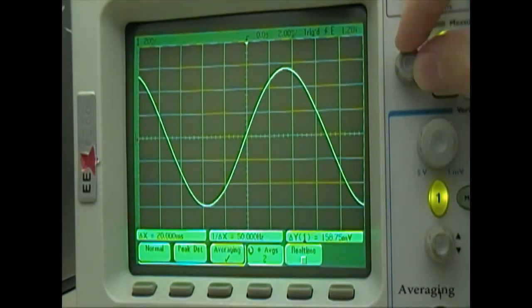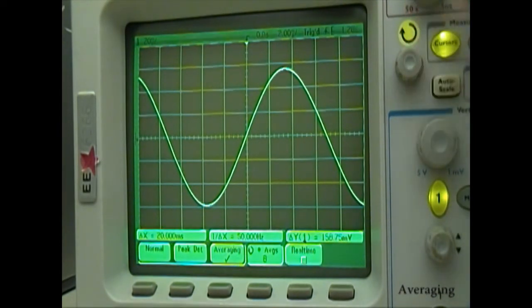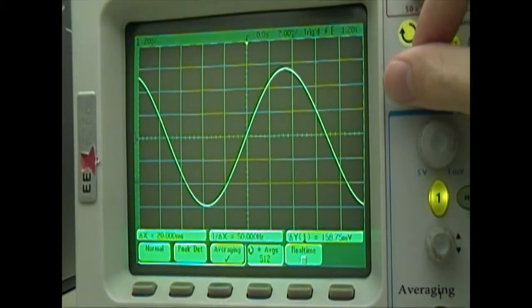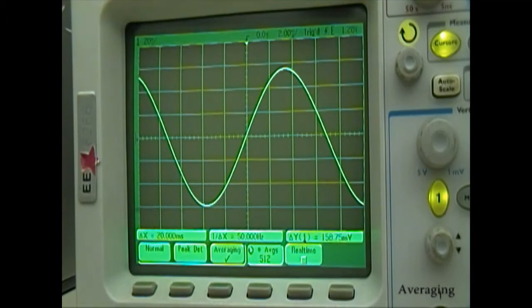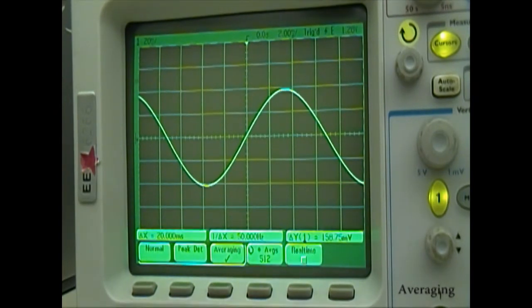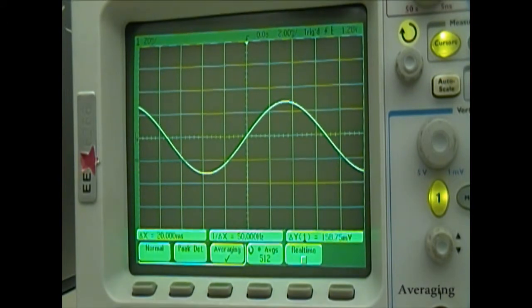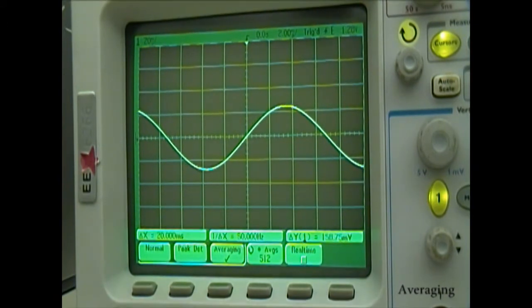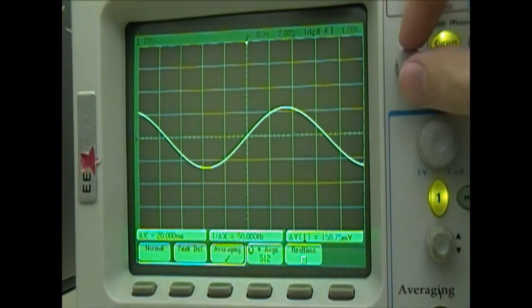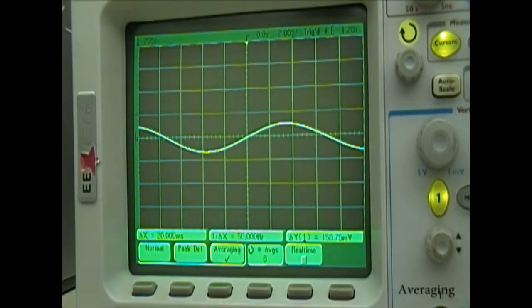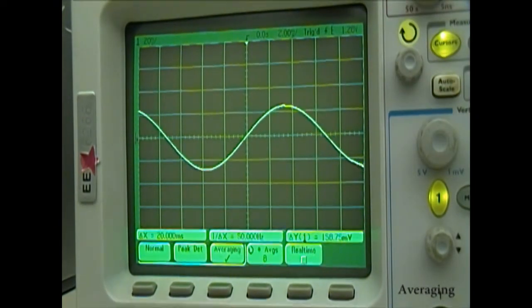In this example, eight averages eliminates our noise, but additional averages may be necessary in other cases. As you add additional averages, it'll take longer for the signal to adjust to changes. Notice how slowly the signal adjusts to changes in amplitude when we're taking 512 averages. But at just eight averages, the signal still responds quickly.